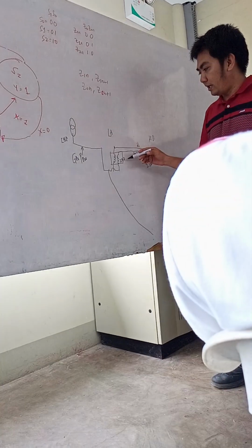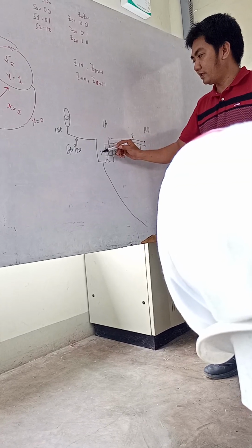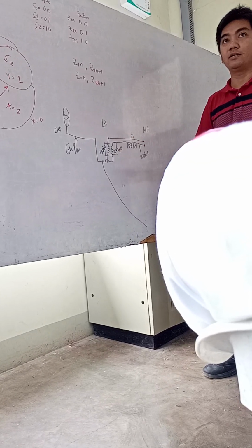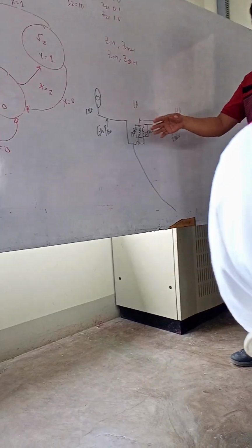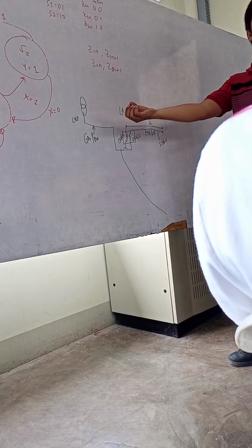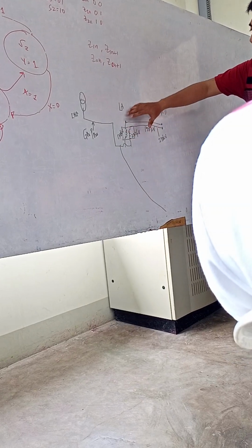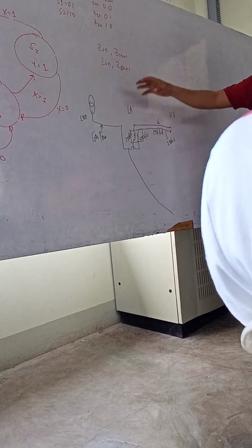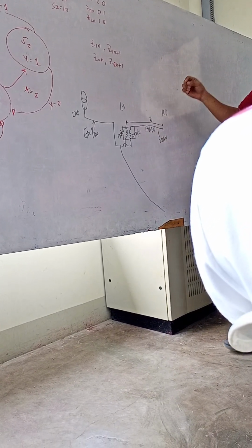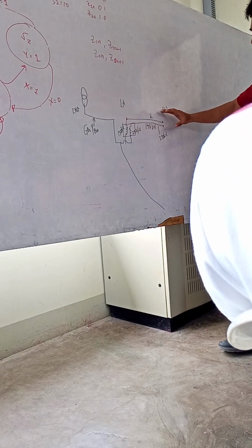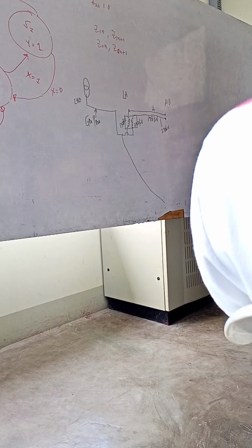The good thing about this is that the 230 kV and 138 kV now share the loading. But more likely, the 230 kV will act as the receiving voltage for generation like GN Power. The meshed network of NGCP is mostly 138 kV. The full mesh is 138 kV. So it is converted to 138 kV, and the 138 kV transmits the power to the rest of Mindanao.